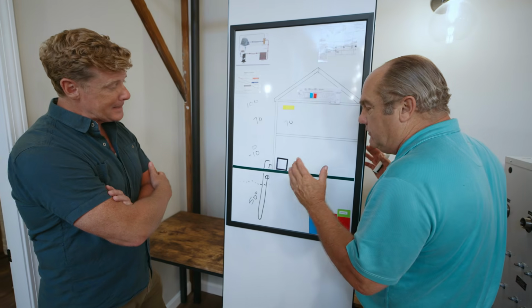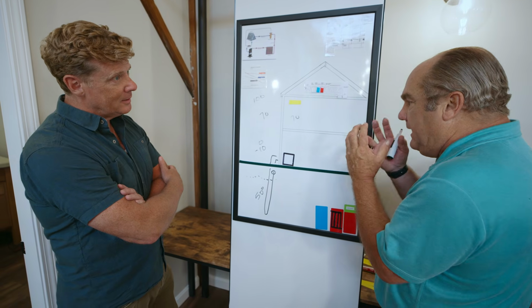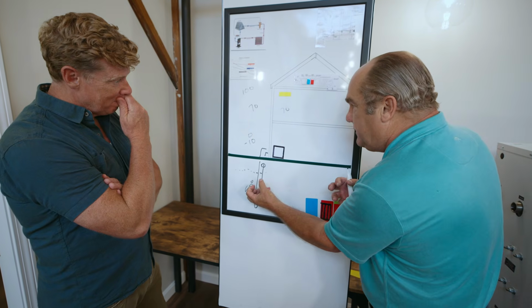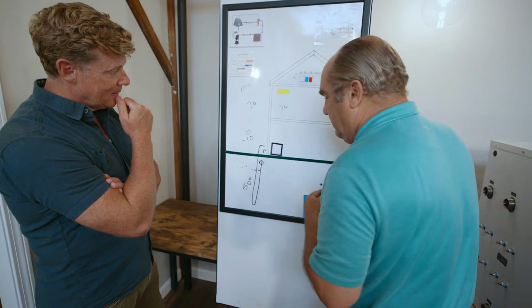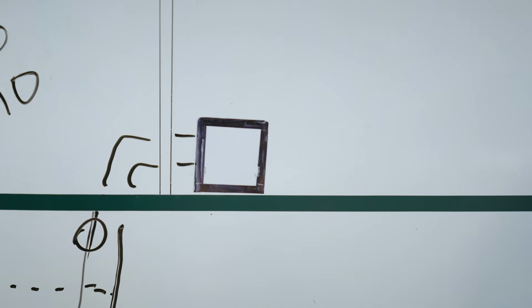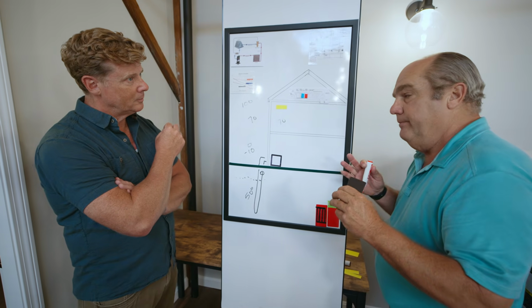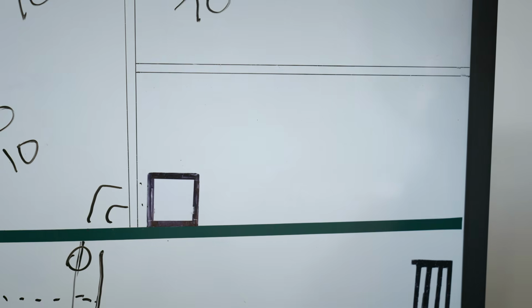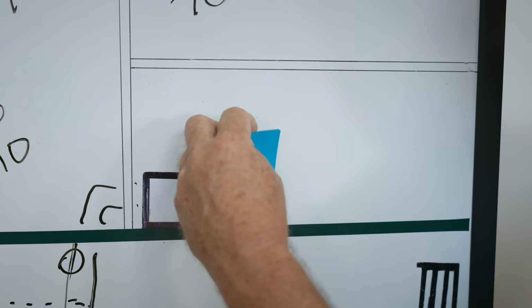That's really the key to it, Kevin. We're trying to move heat, we're not trying to make it, we're trying to move it. So we can find the 50 and easily pump that thing up to get the building to 70. The piping runs into this water-to-water geothermal condensing unit, which gives us a lot of advantages. We want the system to be able to heat and cool different parts of the building at the very same time.